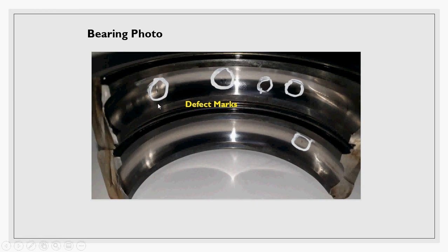This small or tiny notch on the outer race can progress very rapidly in a very short time and crack the outer race — we don't want to reach that stage, as it leads to secondary failure. Your role as a predictive or condition monitoring engineer is to predict the fault before it happens and replace your bearing at the right time. That's all for today — please like, subscribe, and share!